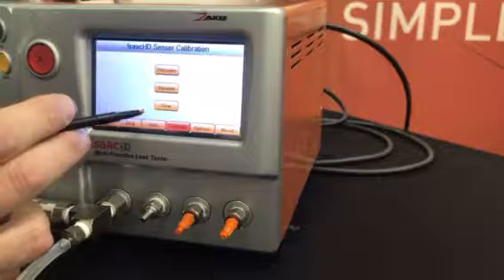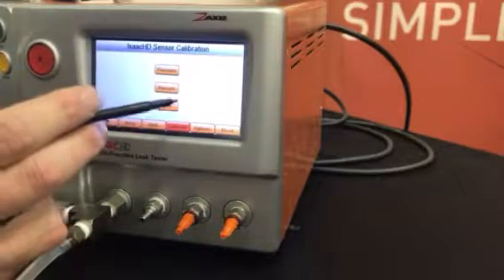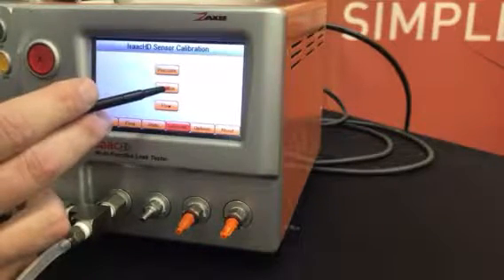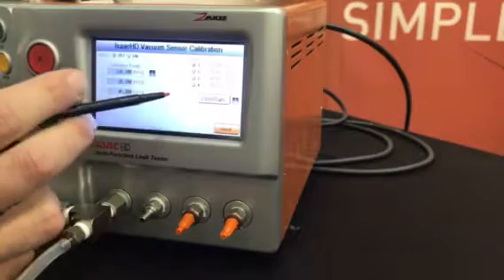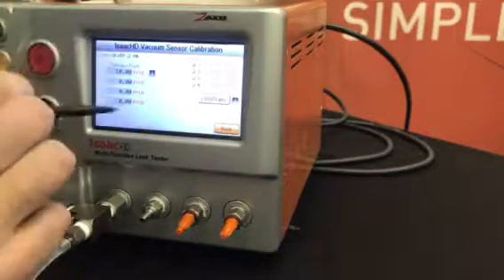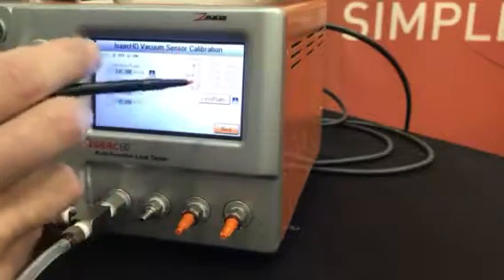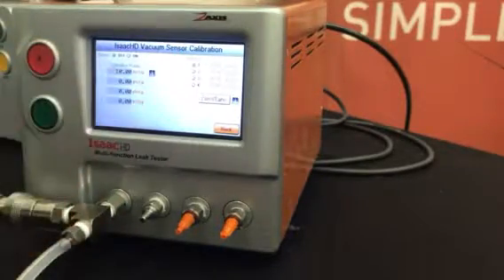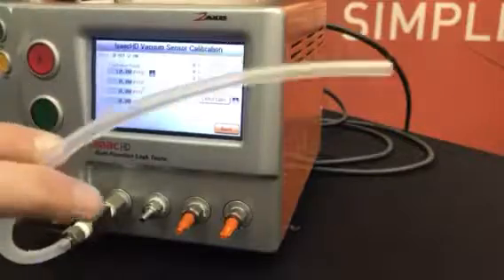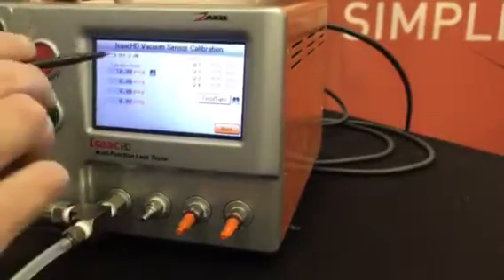and you go to calibration. That gives a pass or warning. First you're going to do vacuum. You have to pull a vacuum on that sensor. You actually have 4 cal points. So as soon as you go to that, whatever that number is reading, press that tare button and make sure it's all open to atmosphere, no air going through it, the valve is still off.